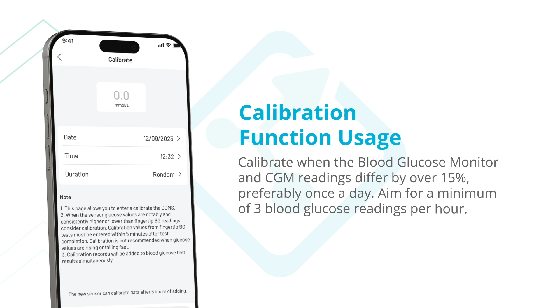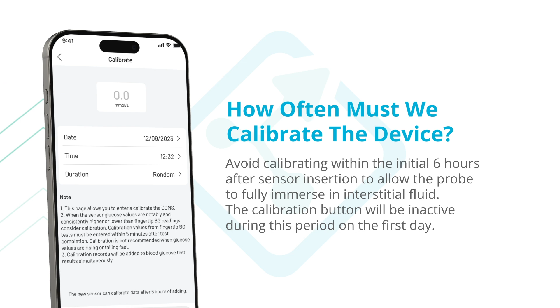When calibrating, we recommend logging at least 3 blood glucose readings per hour until a stable pattern is observed. Calibration cannot be performed within the first 6 hours after inserting the sensor, as the probe requires time to fully immerse in the interstitial fluid after insertion. Users can calibrate the data by clicking the Calibrate button.